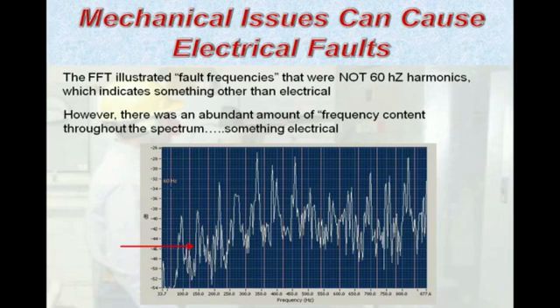Now on the FFT, going back to that, we can see that there are some what's called fault frequencies, but notice they are not taking place on the 60 hertz harmonics. And this is important because electrical faults, when they occur, will have these fault frequencies take place on harmonics of 50 or 60 hertz. When they shift off of that frequency, that leads us to believe it's not going to be specifically electrical in nature. But there is an abundance of frequency noise throughout the spectrum. The activity taking place in between each one of the harmonic cursors does indicate something is occurring with this unit, but we're just not completely sure at this point.